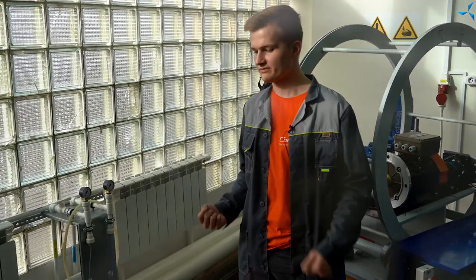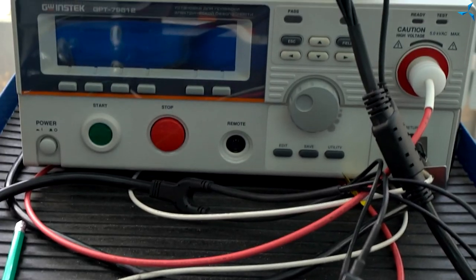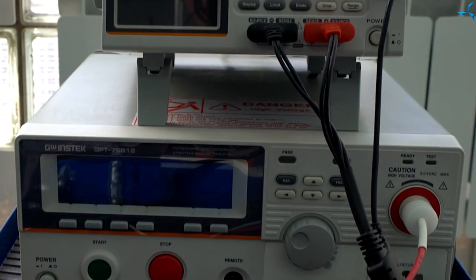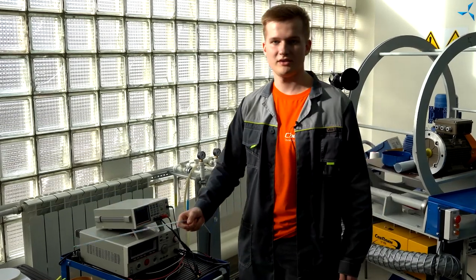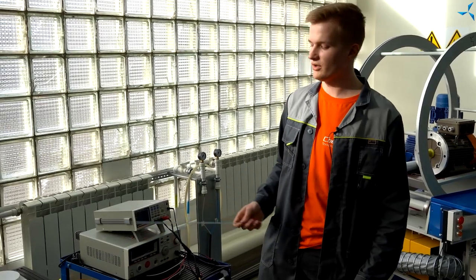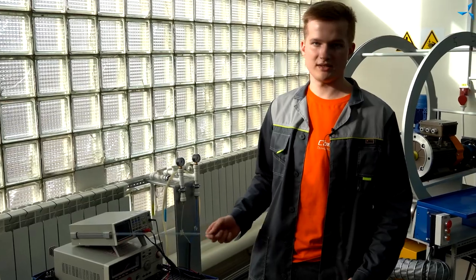The next workstation is equipped with a milliohmmeter and megohmmeter, as well as scales. The milliohmmeter is used to measure the resistance of a particular coil. The megohmmeter is needed to detect insulation breakdowns in the wound motor.